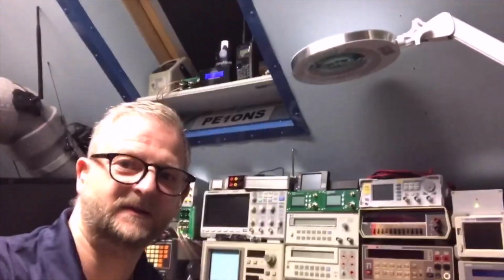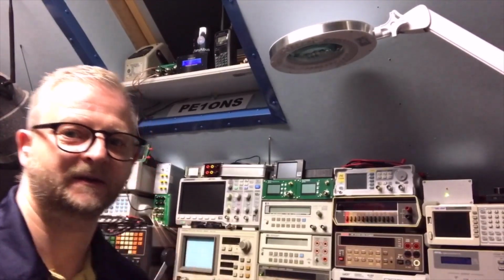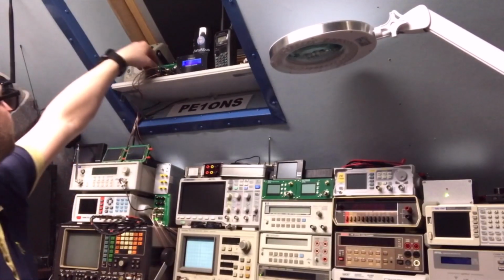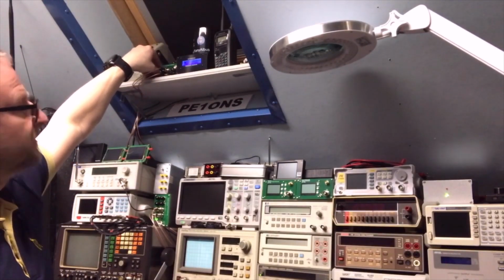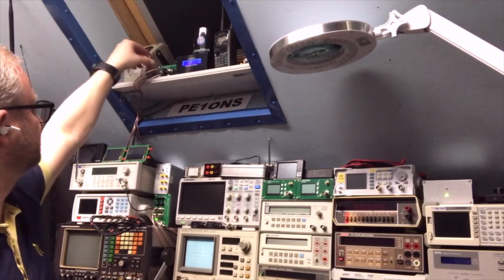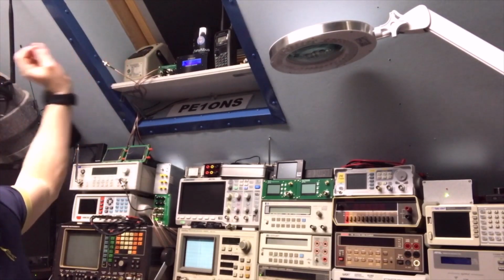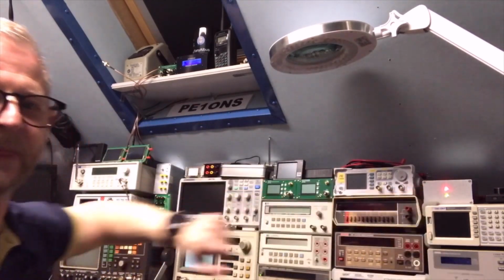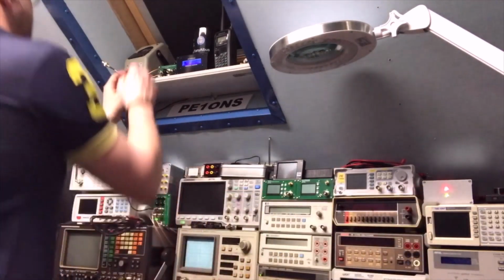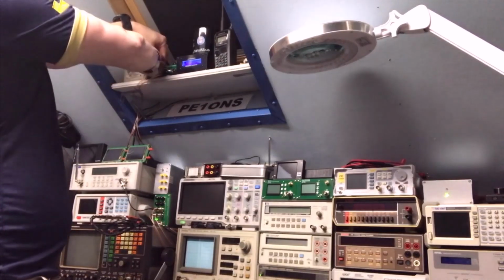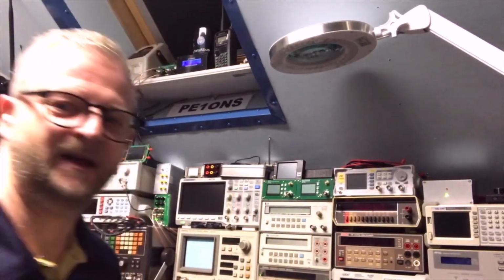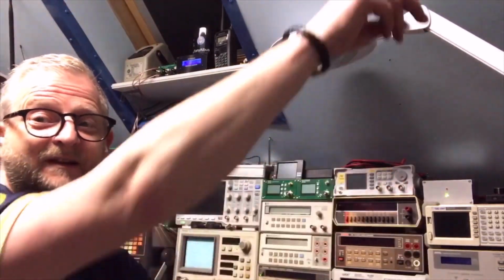And keep an eye on the light here. This light here. If I take it out from the main amplifier, the alarm goes. So now we know, okay, something is wrong. So if we put it back, it will switch off and it will go back to normal. Okay, that is this one. I still have the other one up there.